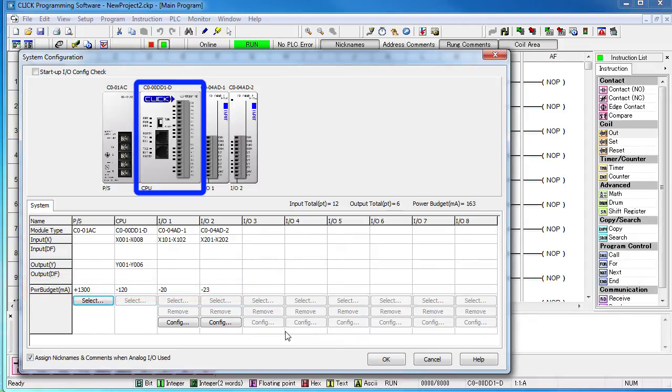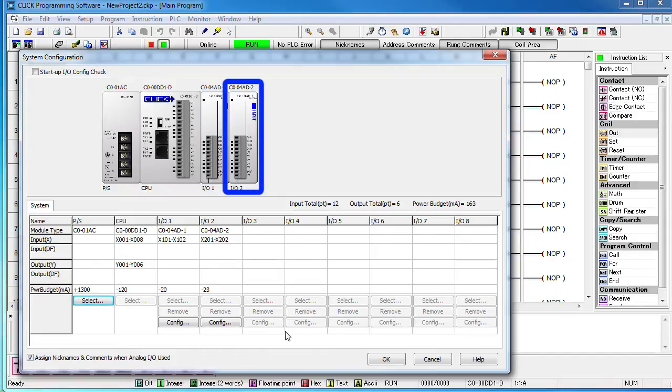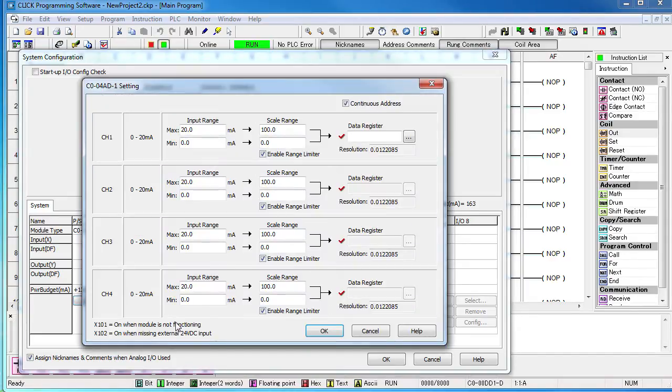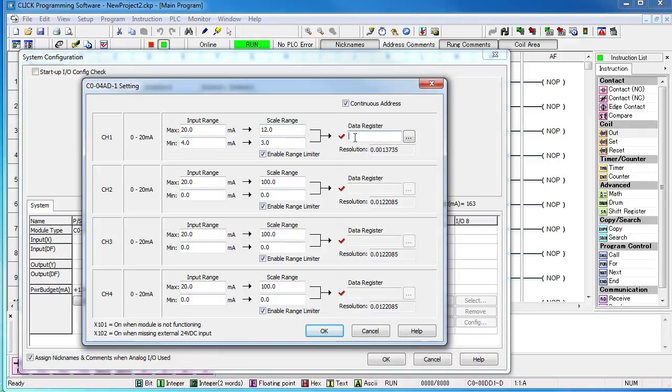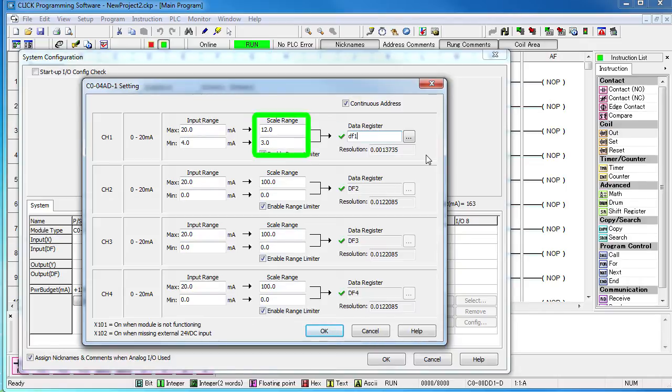We see our CPU in the two analog modules, the 4 input current module and the 4 input voltage module. Click on CONFIG to set up the current input module. Our input range is 4 to 20 milliamps. That represents 3 to 12 inches and we'll put that result in DF1. How cool is that? The CLICK automatically does the scaling for you. The raw value that we get in the ladder code will already be in inches. We don't have to use a separate ladder function to do it. I love that.